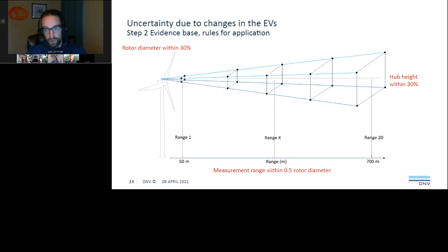First, one of the rotor diameters in the evidence base needs to be within 30% of your test turbine rotor diameter. Next, one of the measurement ranges in the evidence base needs to be within half a rotor diameter of the planned measurement range for your test turbine. And lastly, one of the hub heights in the evidence base needs to be within 30% of the hub height of your test turbine. Again, this is all well defined in the standard.